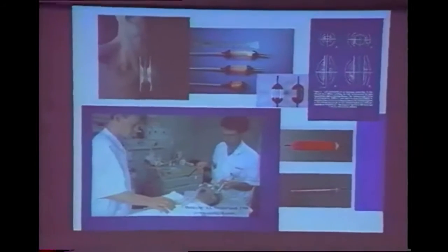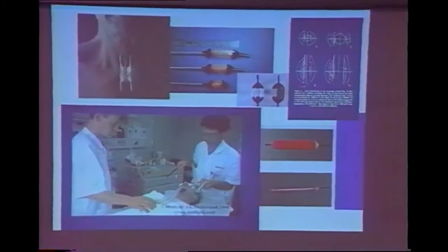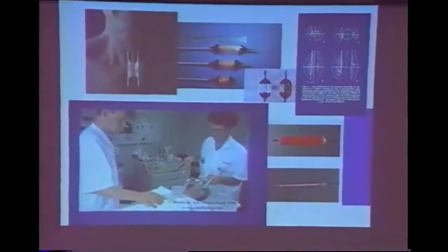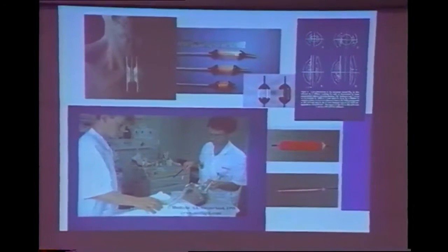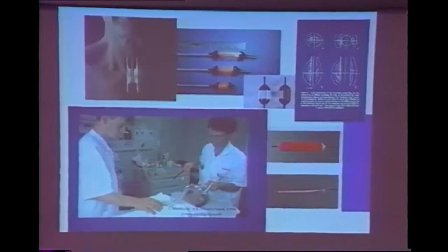As well as the diffusing fibers, a number of groups have developed balloon devices. So here's a balloon device for the esophagus, so that this balloon collapses, goes through the endoscope instrument channel, and then is inflated with air or with water, and once it's inflated, you insert a diffusing fiber through the center, and these come in different lengths. You can shield one side if you just want to treat one side of the esophagus, for example. Again, these are commercially available.